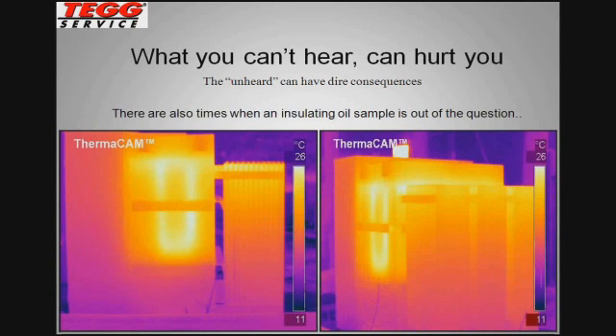With respect to the oil sample, although we're very interested in the combustible gases that show up in these samples, occasionally when you do use the infrared camera, you don't even need to worry about taking an oil sample. On this slide right here, this is an extreme case of where infrared would tell you there's something wrong, even in the absence of ultrasonic emissions. This is a liquid-filled transformer that is 2,500 kVA in New Jersey, and sent to me by one of my technicians. You should never, under any circumstances, be able to discern with this type of detail the windings inside of that unit. And the problem with this unit was there was no insulating oil.